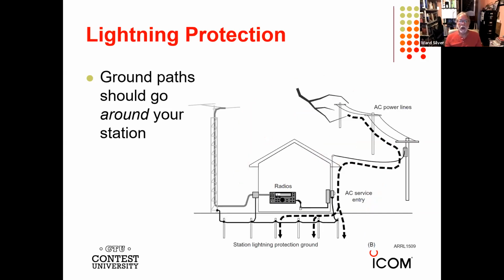Here's what a perimeter ground buys you. So this time Mr. Lightning hits the AC power lines. Here it comes. You've got a big transient. It goes through your AC service entry and it goes to the ground rod out there. Now it might go through the branch circuit, but you've given it this terrific, big, nice station lightning protection ground with lots of ground rods, very low resistance to the soil, which is where it wants to go. So most of that lightning is going to go into your lightning perimeter ground. The tower is connected to it, your service panel is connected to it, all the stuff in your house is connected to it. Give Mr. Lightning what he wants, a big, heavy, direct ground path to the earth.